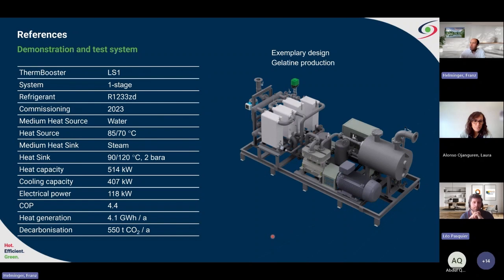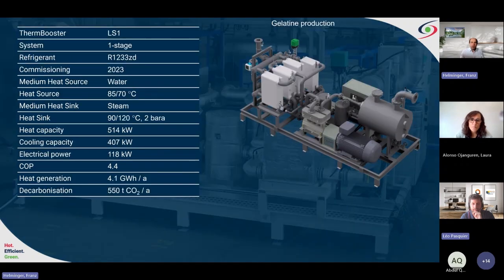Here you have again this LS1 design in a 1 stage. In the first test system, we used this 1233 ZD as refrigerant. We had around 85 degrees C at the inlet of the evaporator, going down to around 70. We generate steam at around 120 degrees C. And the same picture here with 1 compressor on 1 frame, you have around 500 kilowatts. And with these operating conditions, a COP of around 4.4.